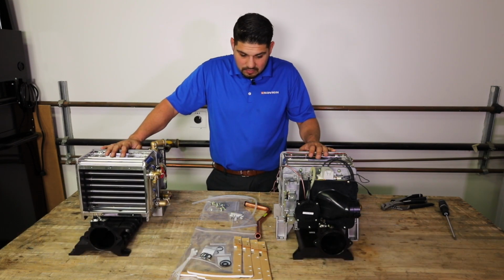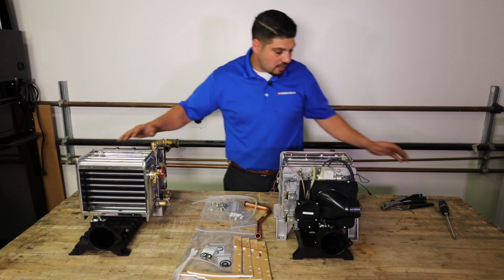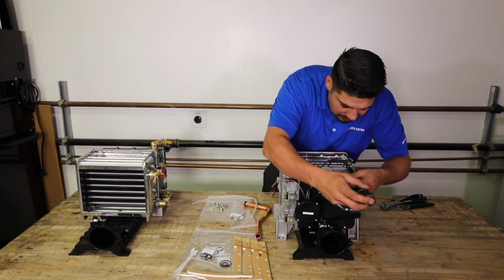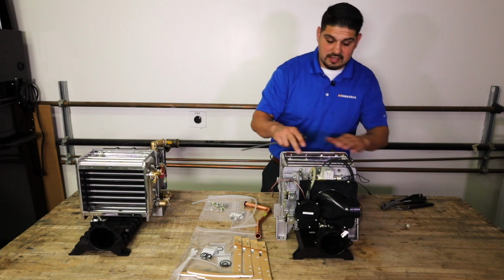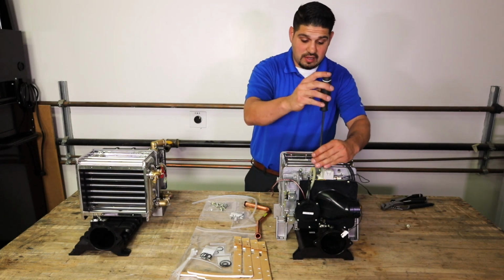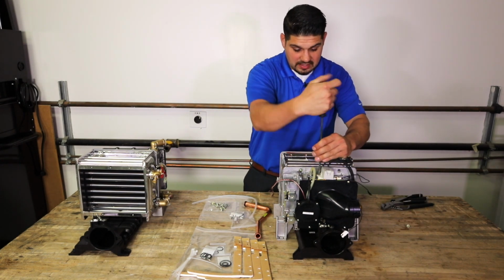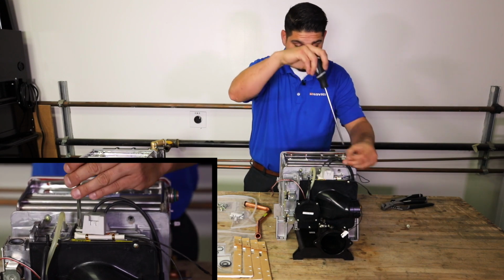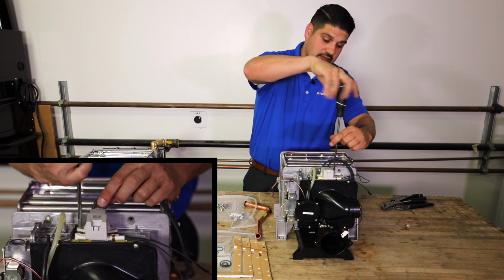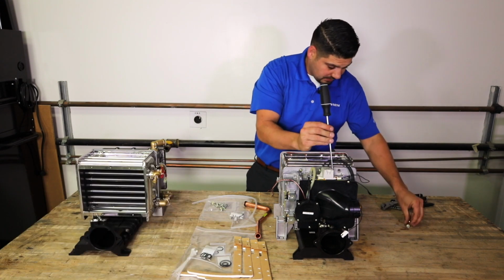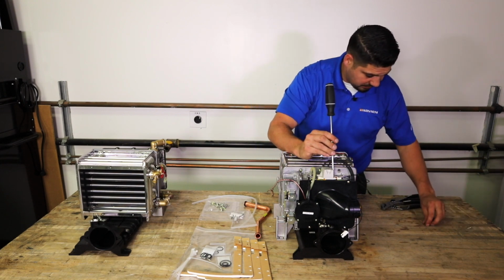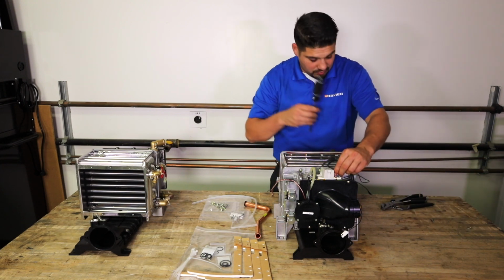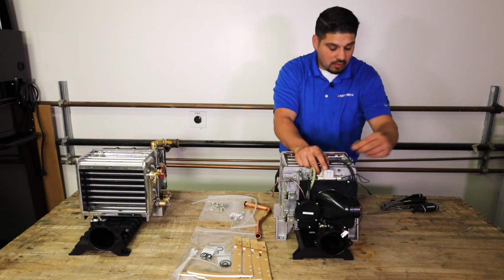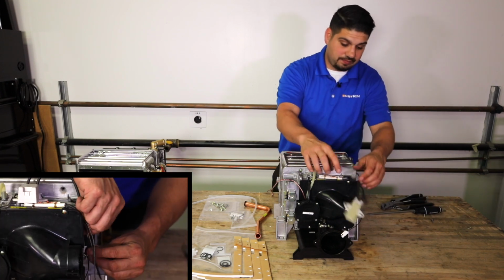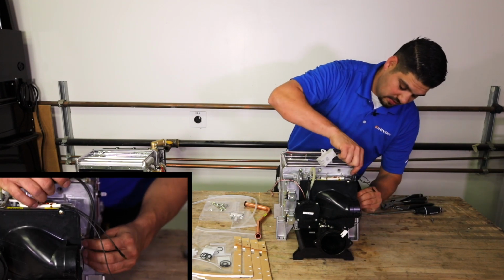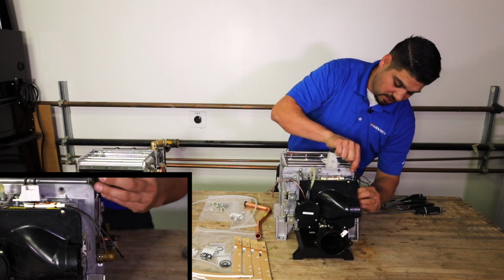So we're going to go ahead and get started here. I'm going to start by removing these screws. In order to access this screw here, we're going to have to take off our ignition transformer. So there's 2 screws on our ignition transformer. Now I'm going to set these aside. There are different screws here. Now something to take note when you're doing this is when you remove your ignition transformer, here we go, it's got 2 wires that are connected to your flame rod.